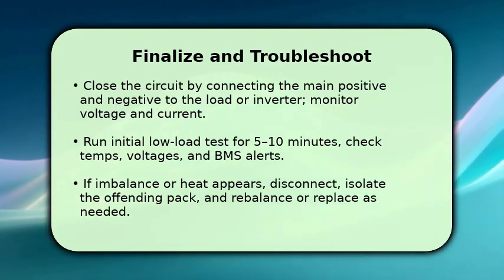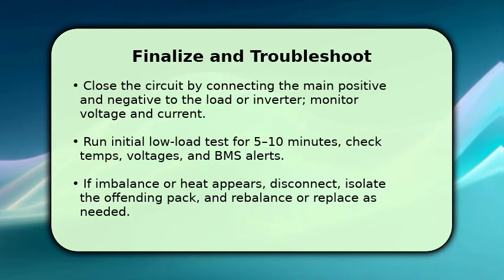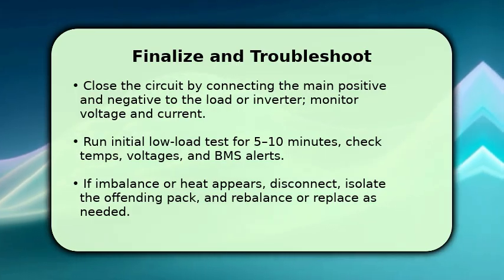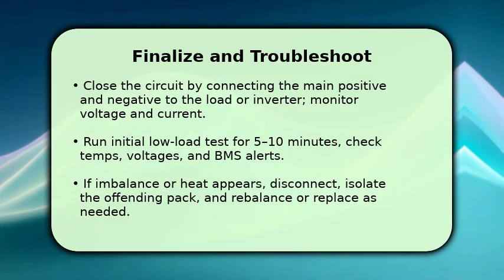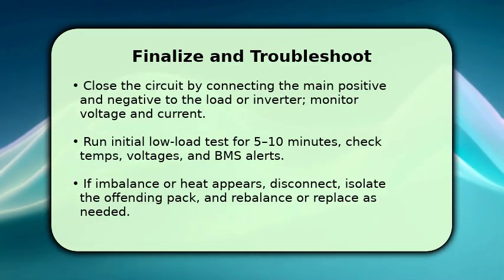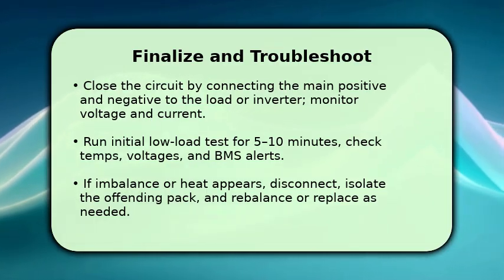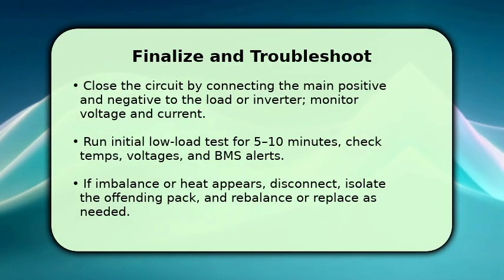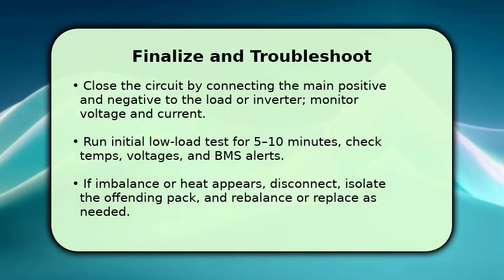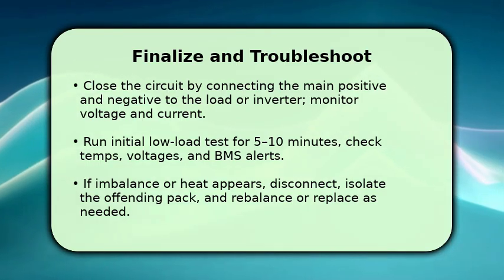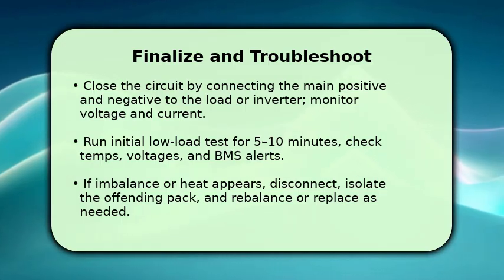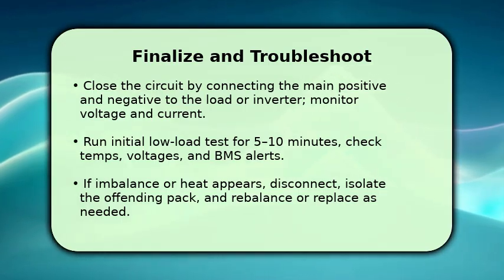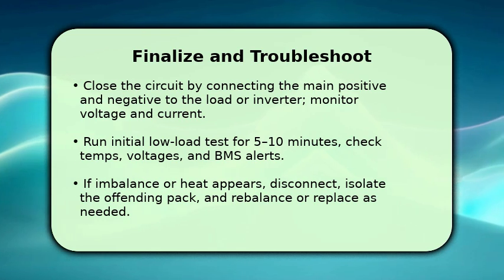apply full load immediately. Start with a low load test for 5 to 10 minutes while you watch voltages, currents, and temperatures at each pack. If everything stays stable and BMS reports normal status, gradually ramp to normal load. If you see voltage drift, unequal currents, or one pack heating, stop and disconnect. Then isolate the problematic pack and rebalance with a charger, or replace it as necessary to protect the string.